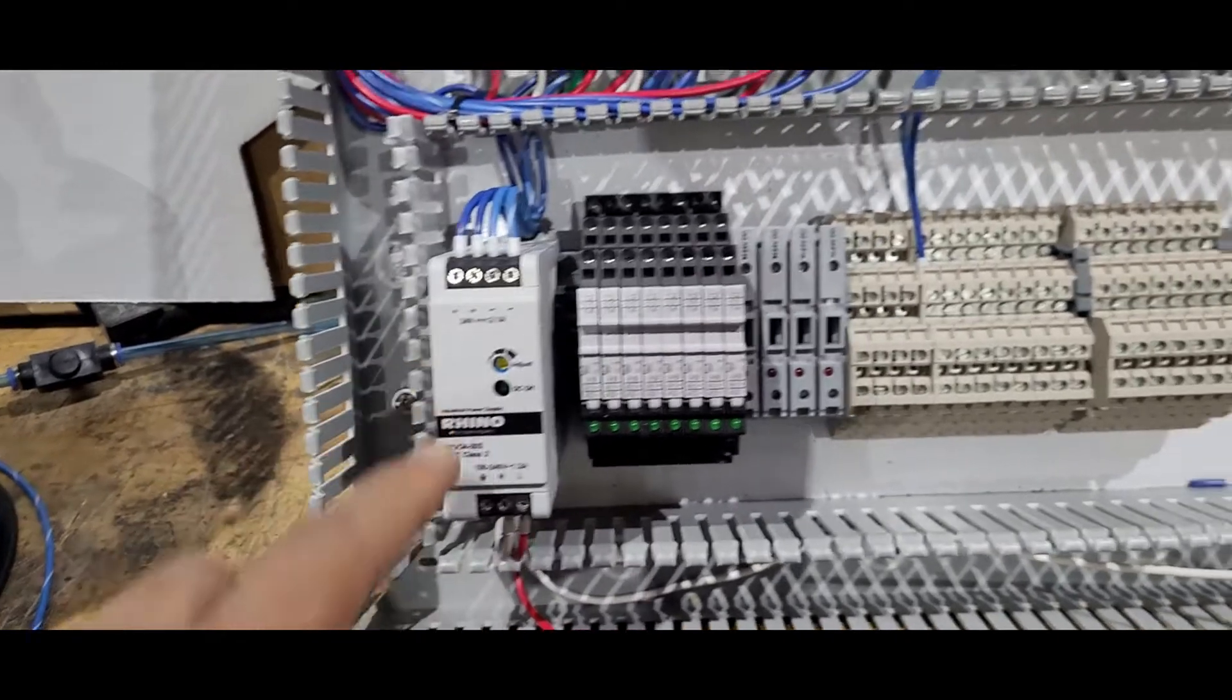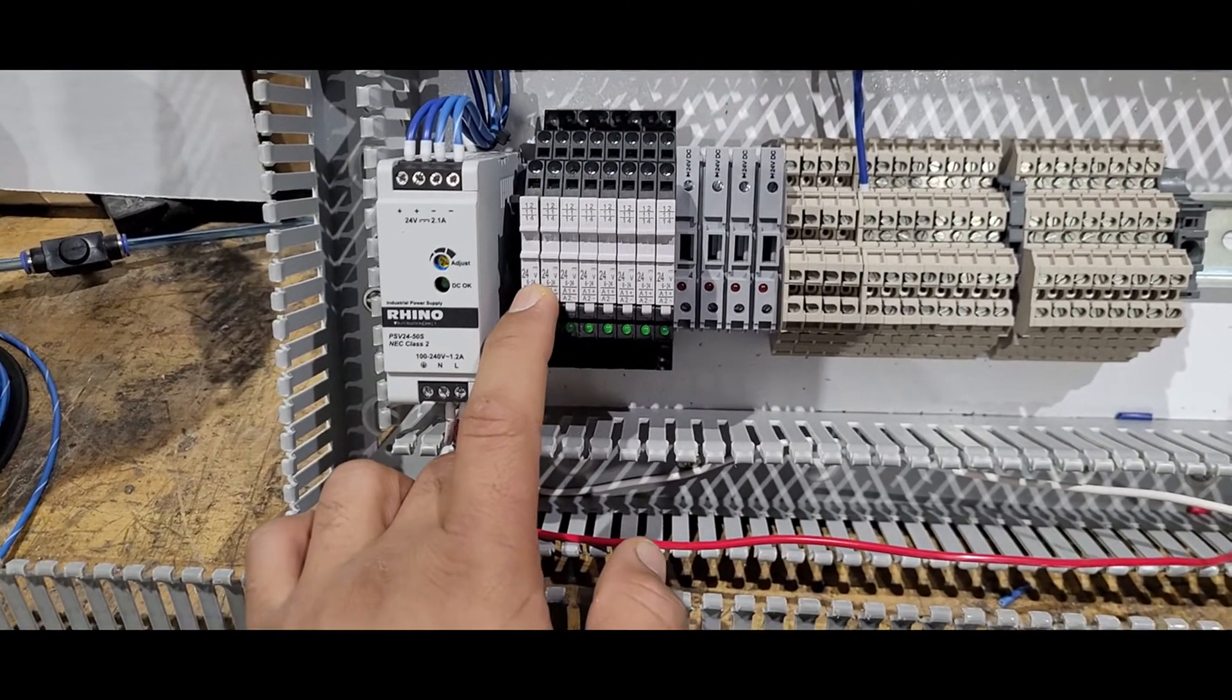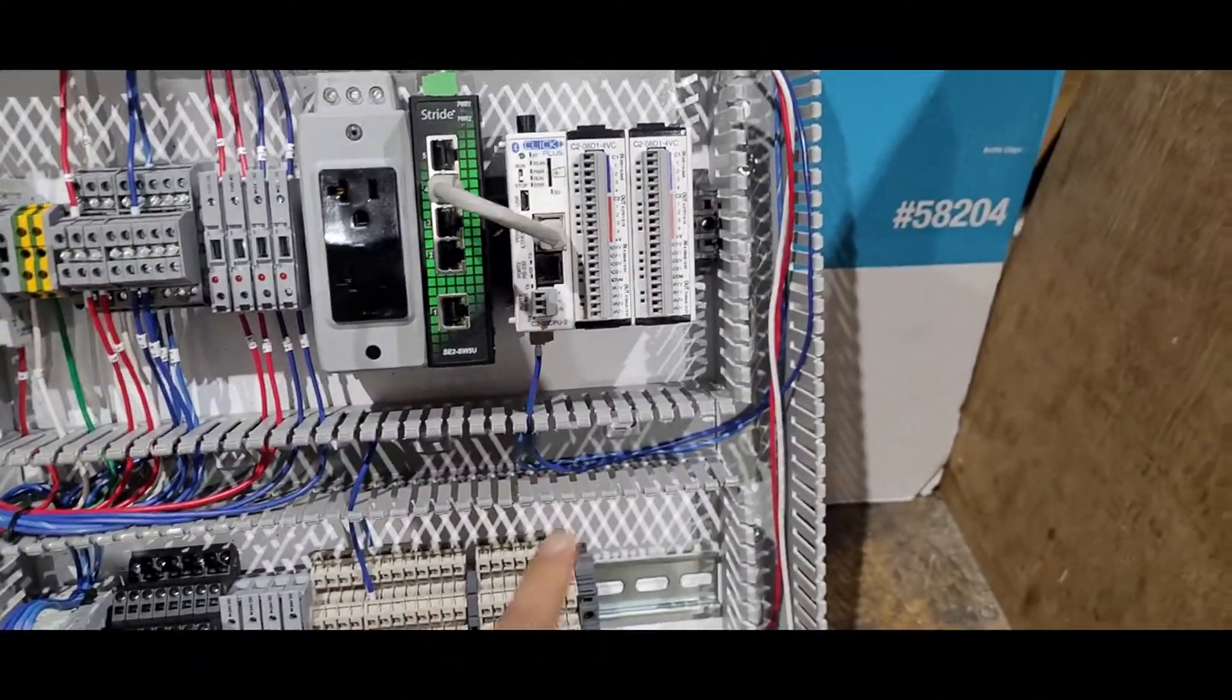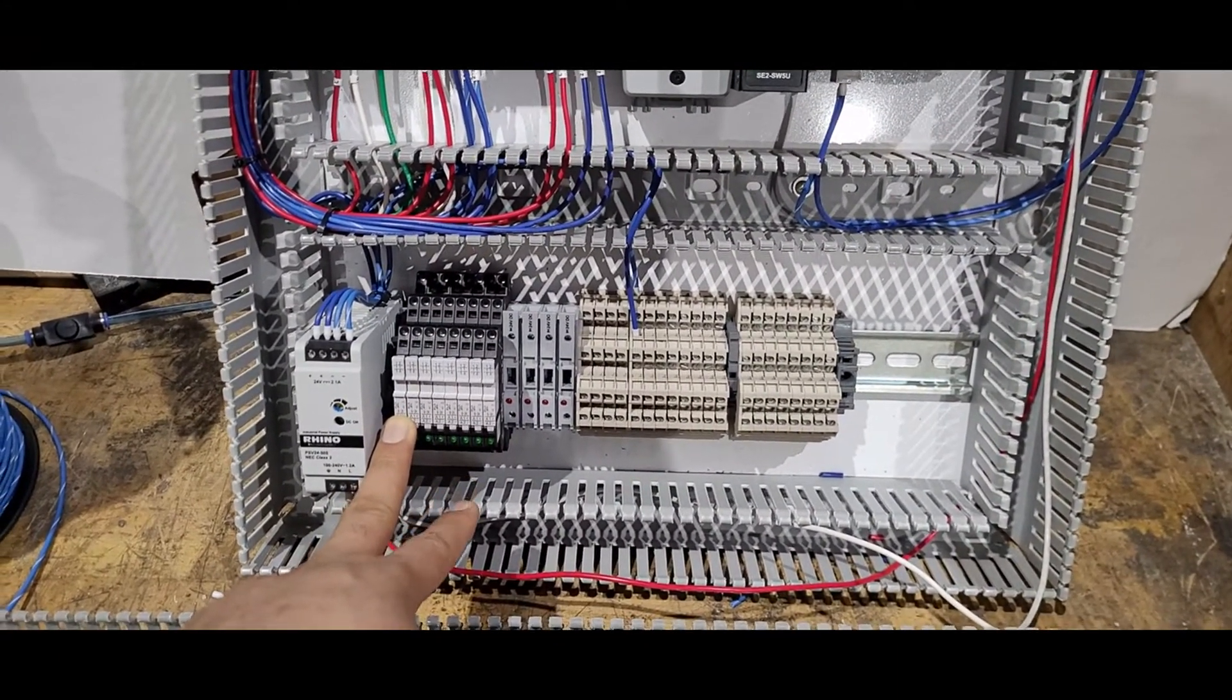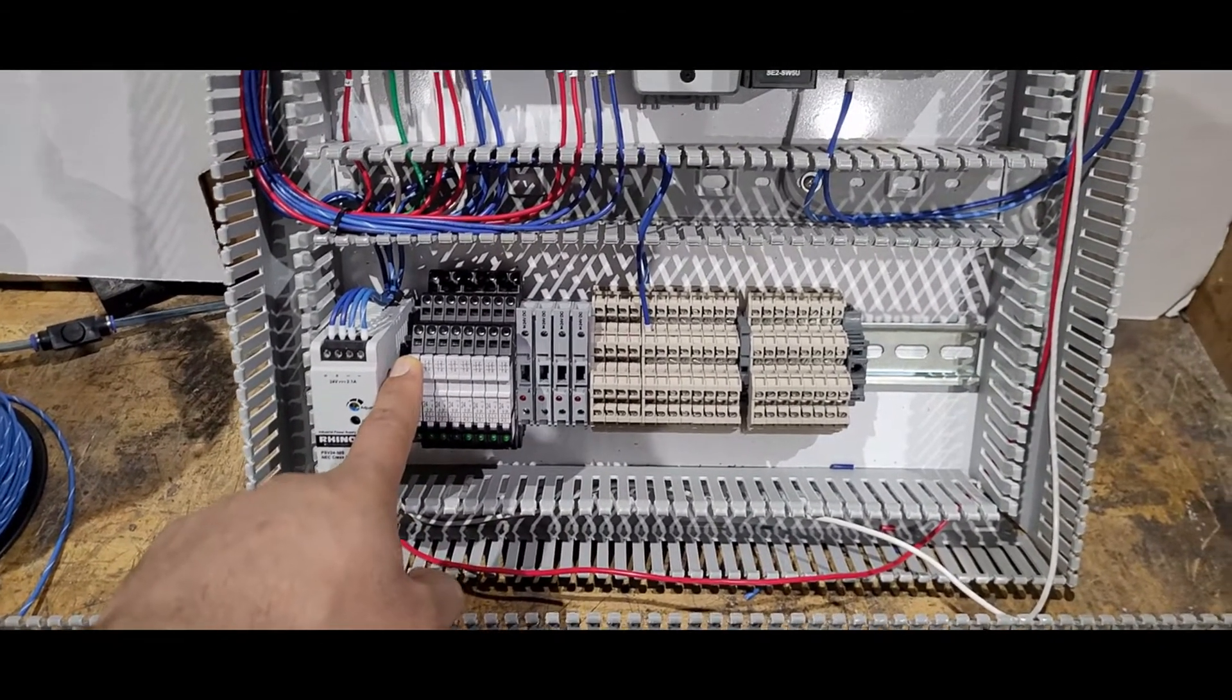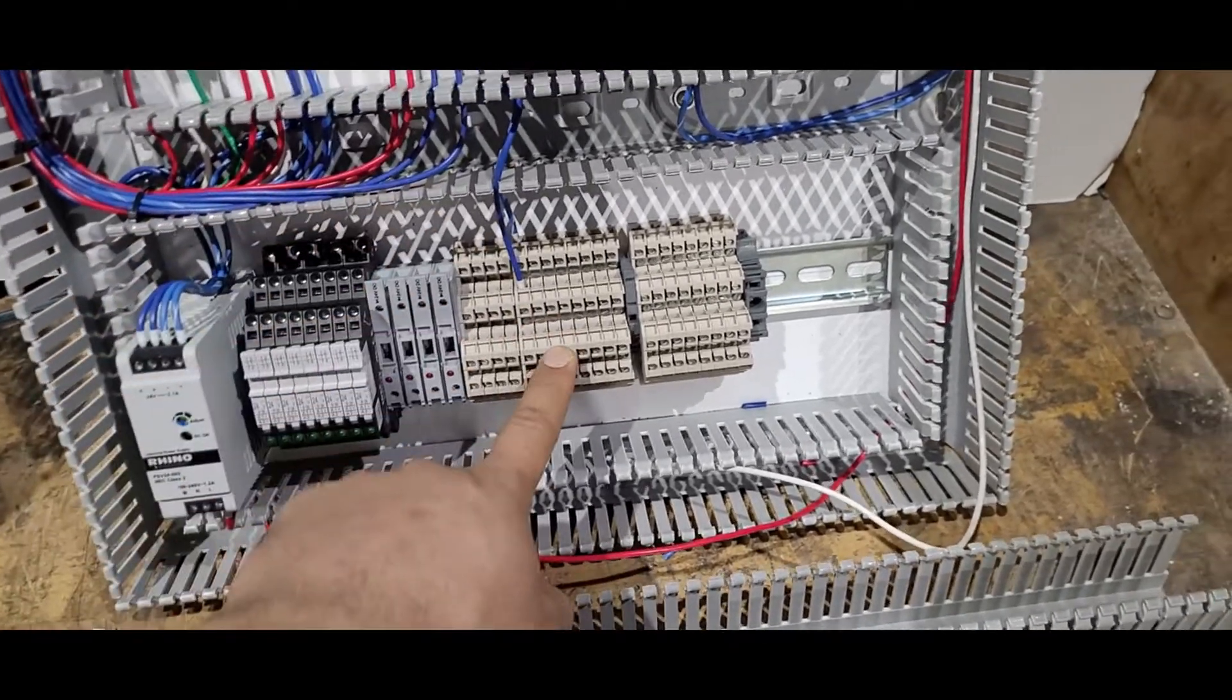Now we have the relays next to my DC power supply. As you can see it's written 24 volt on them, so they work with 24 volt DC which will be provided by this DC power supply. These relays will be energized with the help of the outputs from this PLC. They will be energized according to my application requirement. Let's say if I have to activate a valve, when relay number one energizes it's going to activate my valve which is connected in the field outside.